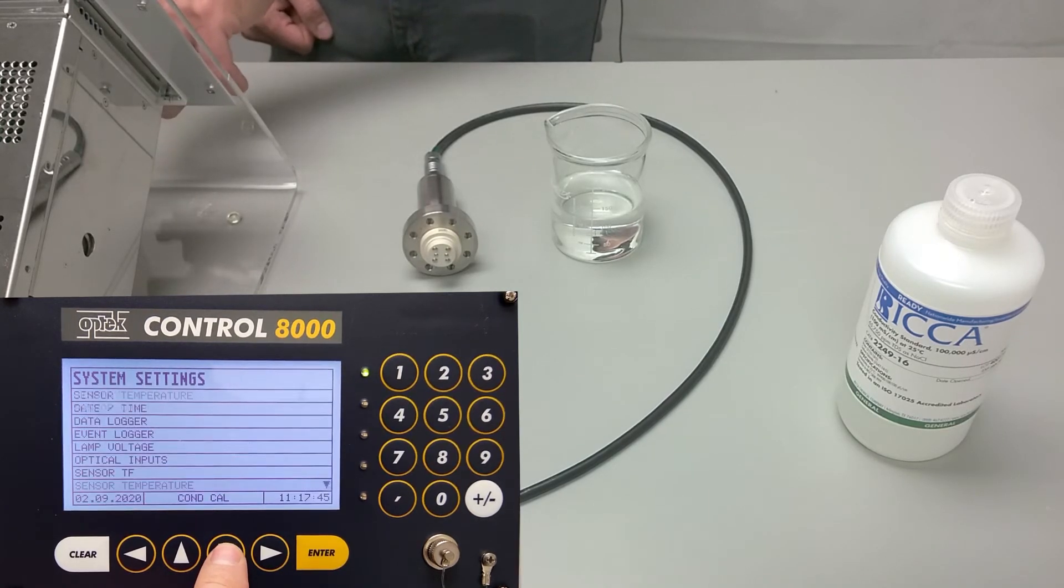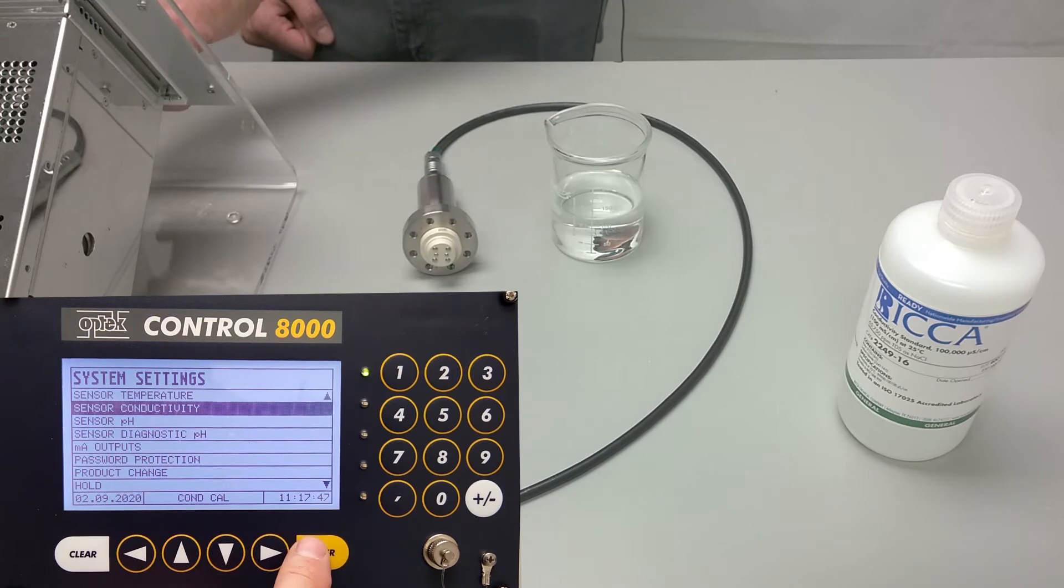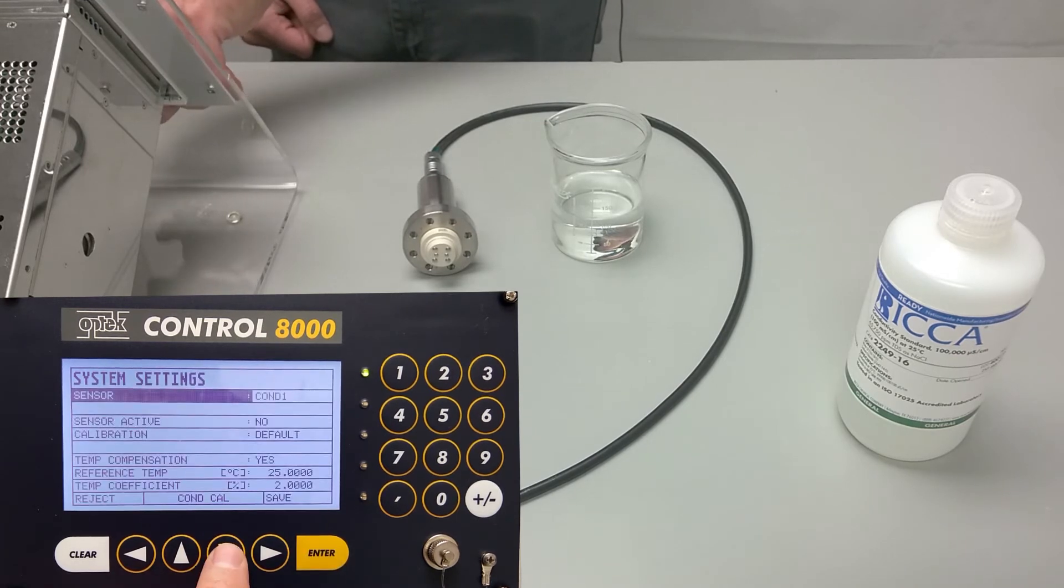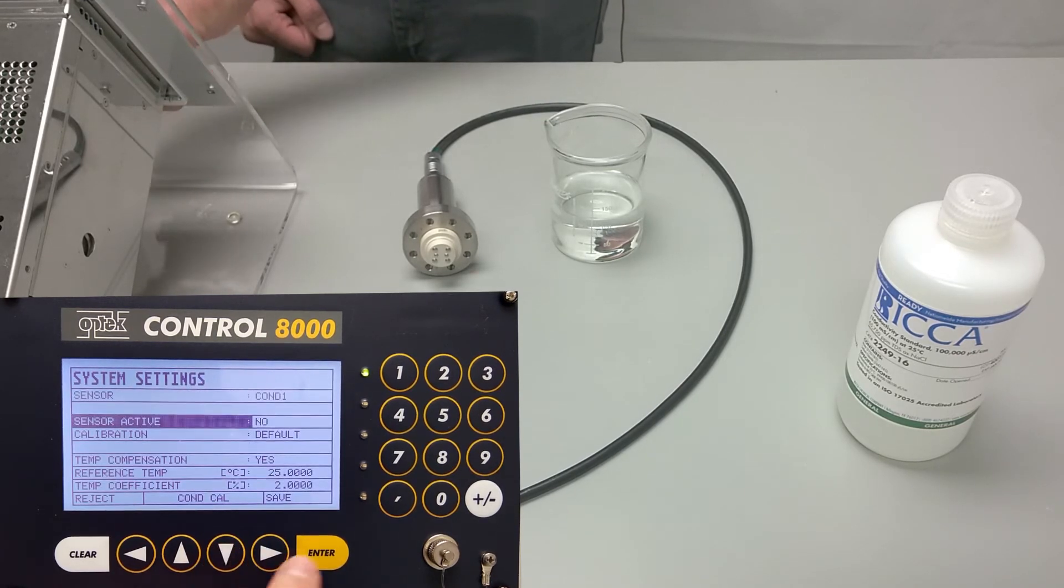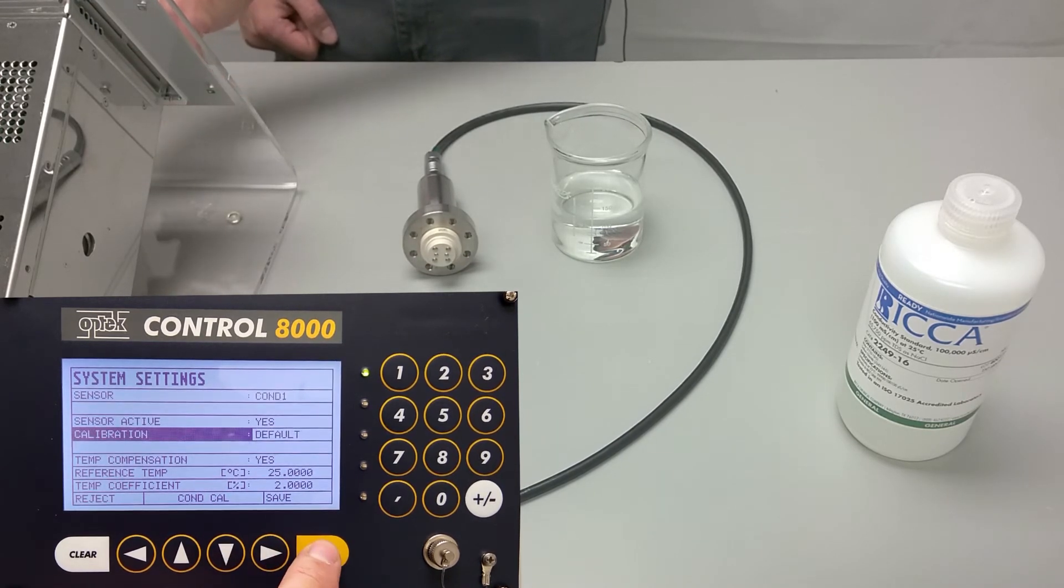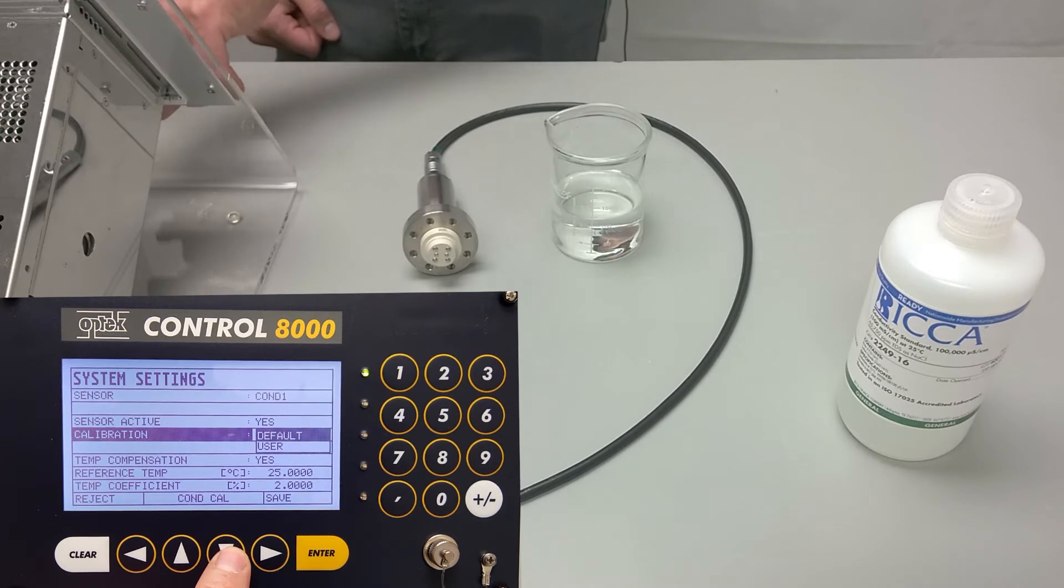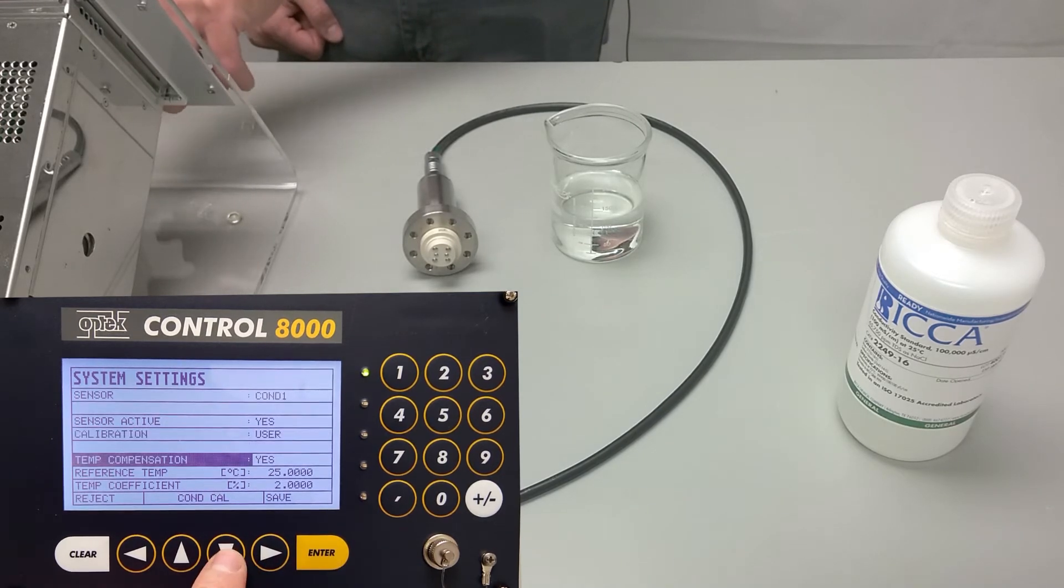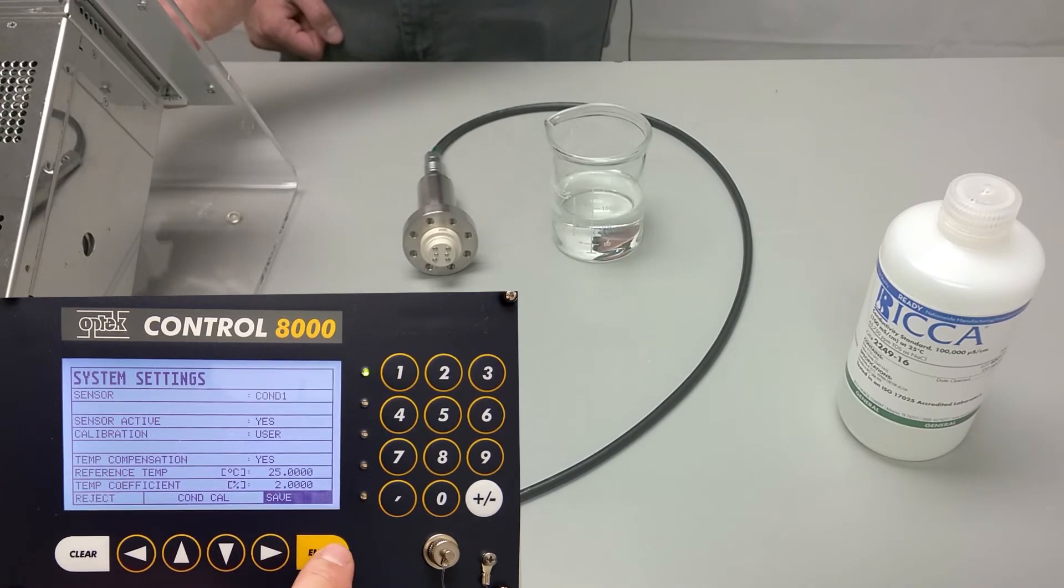Press down to get to the next menu for sensor conductivity, press enter. Again, COND1 is selected and change sensor active from no to yes. We'll also change the calibration from the default factory calibration to the user calibration we are about to perform, and then we'll save our changes.